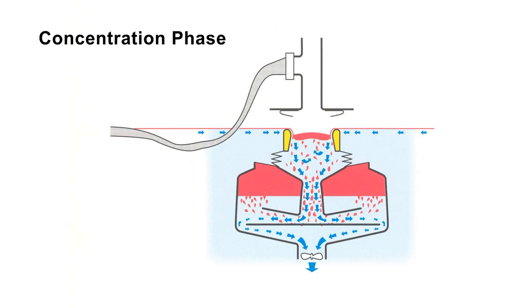In the concentration phase, downward water flow pulls the surface pollutant down inside the SurfCleaner. Deflection discs force the water and pollutant out to the sides, dramatically lowering the flow velocity. This makes the pollutant rise towards the ceiling of the collecting tank, while the water continues down and past the propeller.